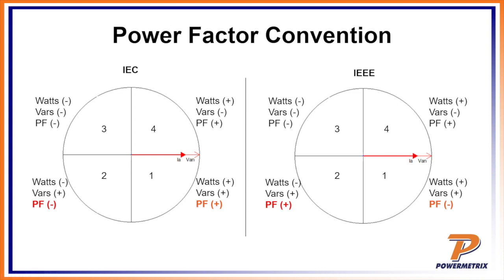The reason why this issue came up is I was dealing with a customer, and he was reading his meter on SCADA. SCADA was reporting a non-update value. That means SCADA could not recognize a negative power factor, because the meter was in that quadrant 1, it was kind of shifting, so it could not see the negative value at all.